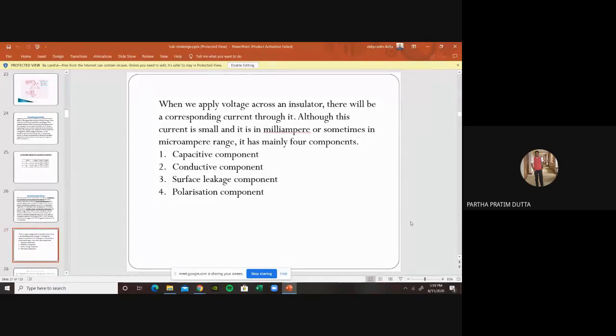Then here are certain situations why we do the insulation test so frequently, which I have explained over here. If you apply voltage across the insulator, there will be a corresponding current through it. Although the current is very small, in the milliampere or microampere range, why is this current flowing if it is absolutely insulating material? It is because of 4 components: the capacitive component, conductive component, surface leakage component, and polarization component. These 4 components are the reason for this current, although it is in the milliampere or microampere range in the case of the polarization test.